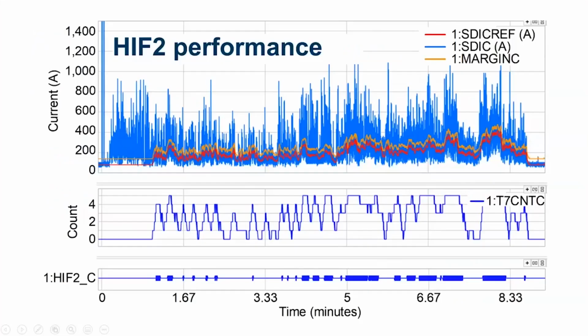What the relay does, as Anthony explained, is look at the SDI, or sum of difference currents. Since we're talking about the fault on C phase, I'm going to look at the sum of difference currents for C phase. This blue line is the sum of difference currents, or the arcing seen by the relay. This red line is the SDI reference developed by the relay. The relay compares the reference with the actual SDI. And lastly, there is a margin added for ambient load. There are changes in the load which can look similar to a high impedance fault, so the relay adds a certain amount of margin to the reference.